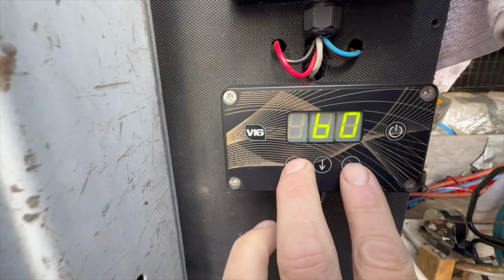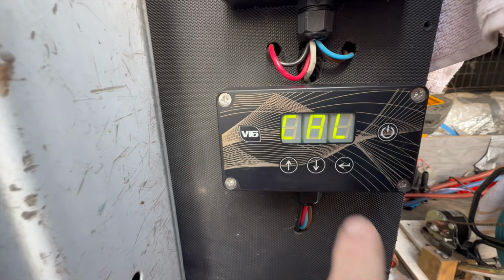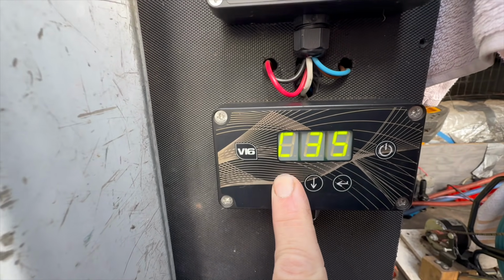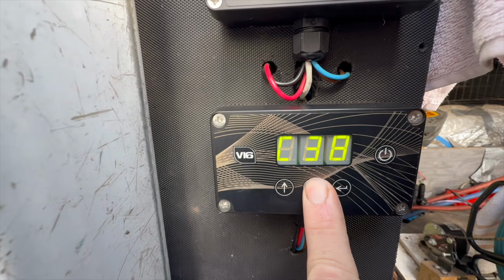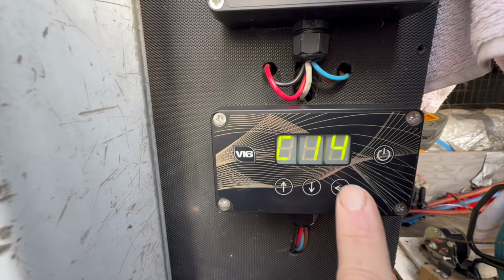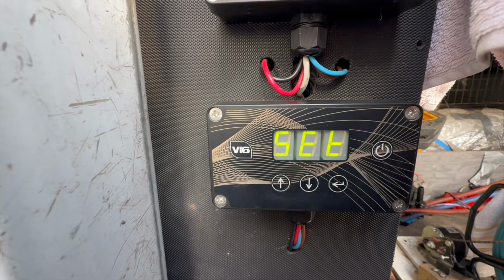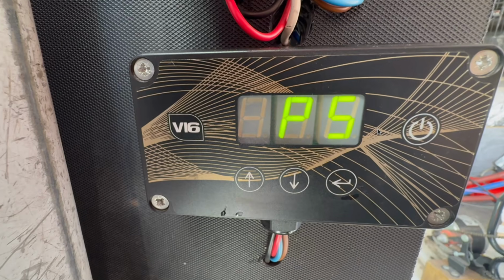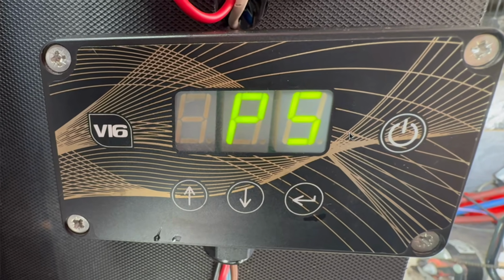So with dead end, you can basically set your dead end level, can't you? You can. Which you do through the auto calibration. Correct. Now you can also manually set that. So what will you see if your dead end is set too high? If it's too high, you're going to find that you won't get DE on the controller. You'll get pressure switch. You'll see the P5 message.